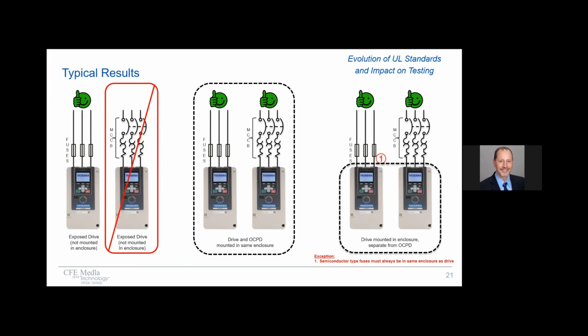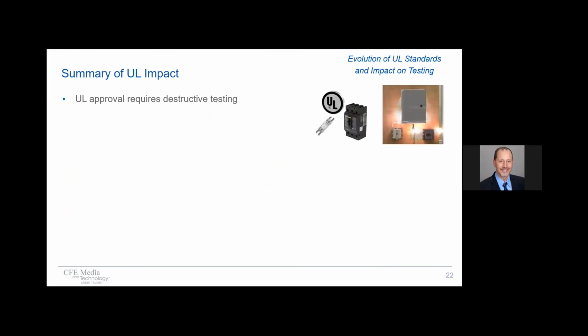Again, I want to stress that what's shown here is only typical results. When choosing protection according to drive supplier's instructions, you will definitely find variation and detail that you need to be aware of. We're going to take a look at a quick example of such instructions from a drive supplier, but before we do that, I just want to recap the impact of UL. First of all, UL requires this destructive testing. The test result is greatly affected by the choice of the protective device.